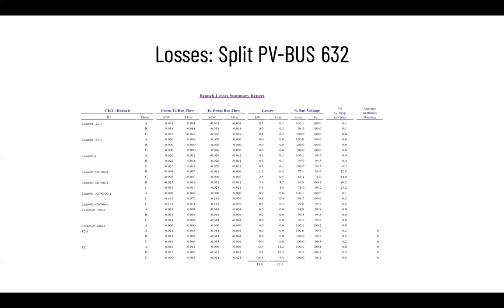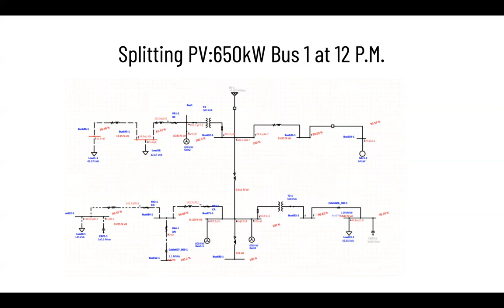All right, so I did a similar case of splitting it as well for the generation of 650 kilowatts. What I did was split it into two, in half, and bring it over to the residential side onto bus one on the top left. And we can see that the condition is under voltage, meaning there's a big voltage drop in the residential area. This voltage drop can come from many factors, such as the transformers, the loads, or just something inside the residential area that's causing the under voltage. This big voltage drop is about 10 to 20% when running it.